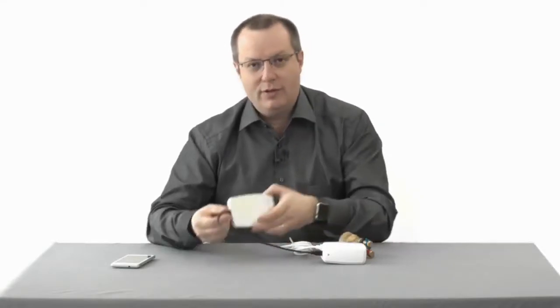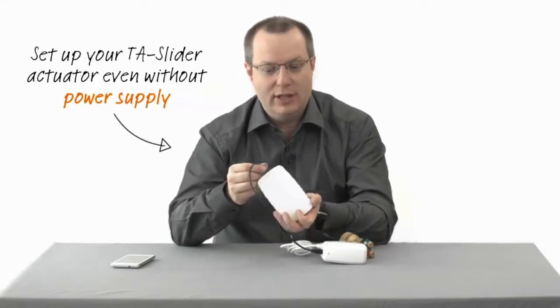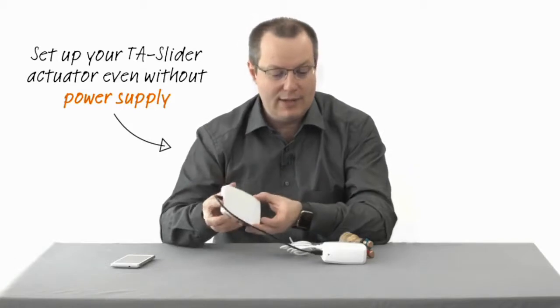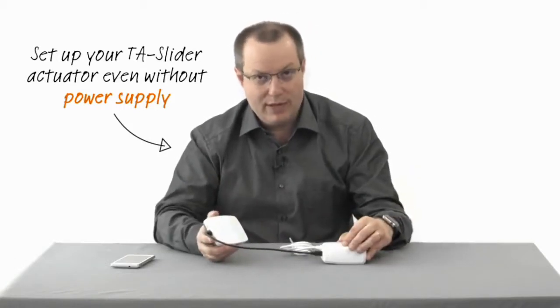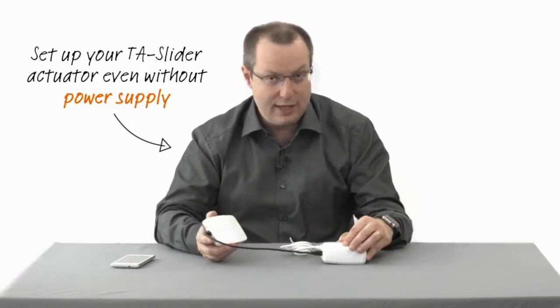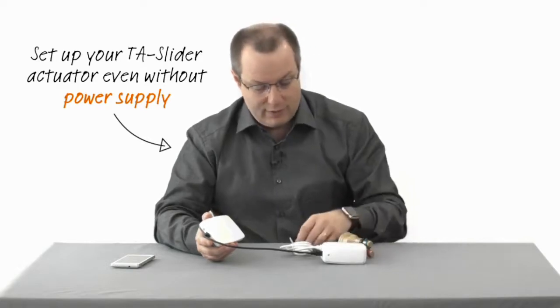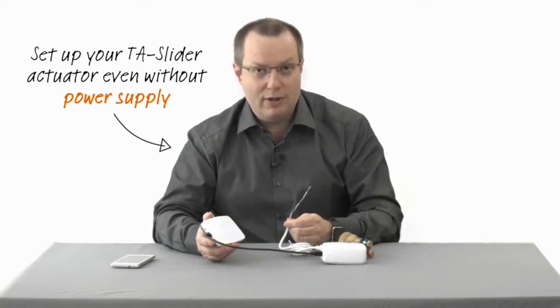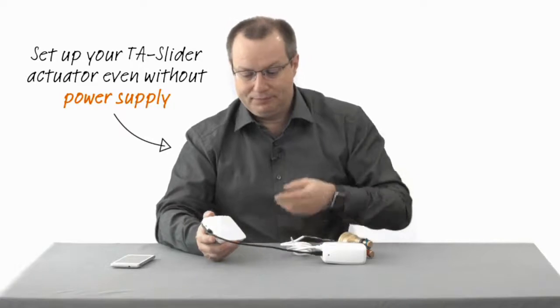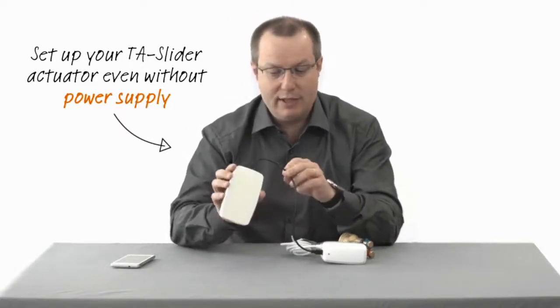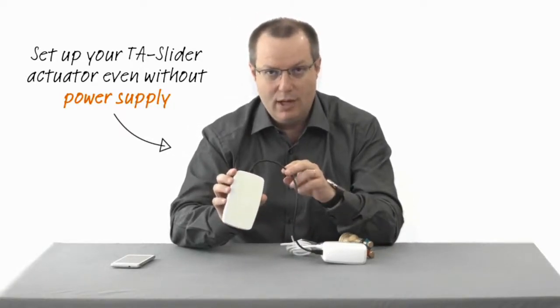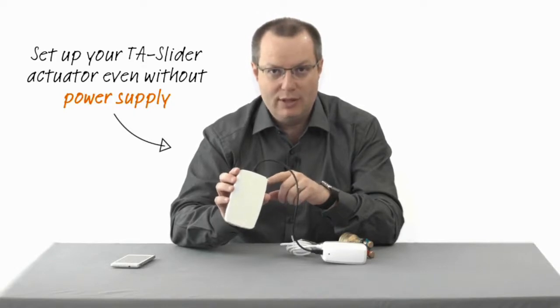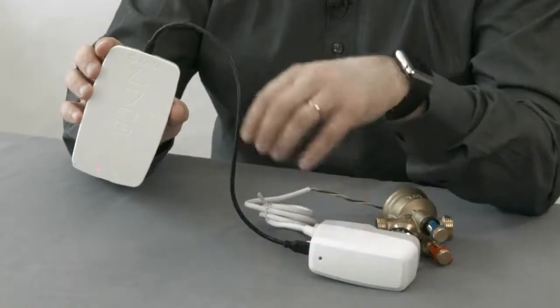One of the good features of having the TA dongle is that its battery is sized for powering up the Slider 160 and TA Slider 500, even though these actuators are not connected to the power supply. This means that by connecting the TA dongle to the actuator, you get an easy way to position it at a first position during commissioning time.